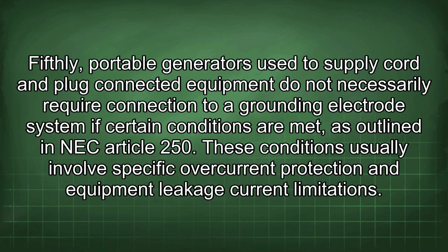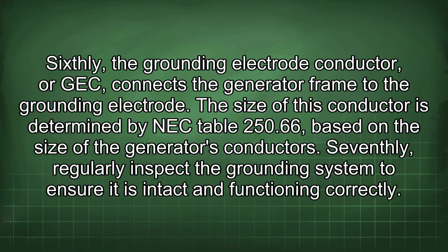Fifthly, portable generators used to supply cord and plug-connected equipment do not necessarily require connection to a grounding electrode system if certain conditions are met, as outlined in NEC Article 250. These conditions usually involve specific overcurrent protection and equipment leakage current limitations. Sixthly, the grounding electrode conductor, or GEC, connects the generator frame to the grounding electrode. The size of this conductor is determined by NEC Table 250.66 based on the size of the generator's conductors.